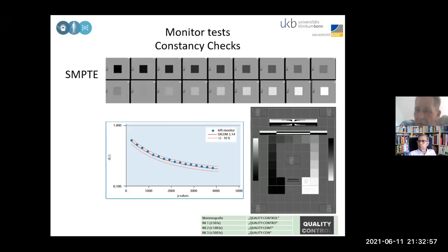Because in mammography you actually see pixel-wise. It's not like chest X-rays. In chest X-ray you don't look at the pixel, but in mammography you look at the pixel. So the pixel is your real value to look at, and so the SNR is not even giving you a hint. You really have to see that the SNR meets the requirements which are given, and they're usually less than 2%. The noise should be less than 2% of the average. So if you have a homogeneous phantom of a certain thickness, the noise will have to be less than 2% of the homogeneity. The entire formula I could give you, if you would like to have it, then write me an email. I think that would really exceed the talk right now. I'm sorry. Would that answer your question for the first hand?